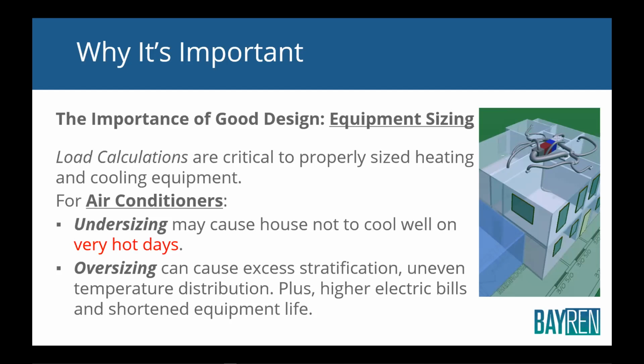Now for air conditioners, if you were to make a mistake in your load calc and undersize an air conditioner, and that means the capacity of the air conditioner is less than the load on a design day, that one percentile day, that air conditioner is going to work very well on all but the very hot days. So most of the time, that undersized air conditioner will work fine. It's only on those really hot days that it doesn't work.